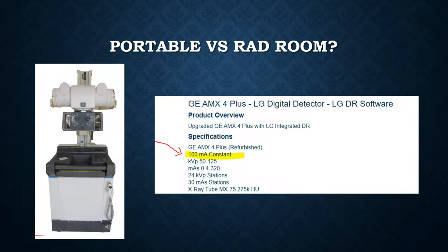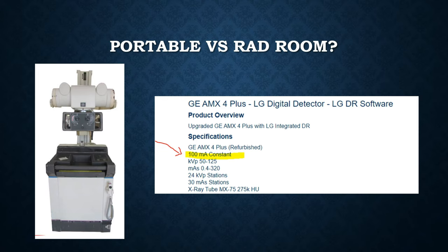Most portable units are set at a fixed 100 mA station. If you need 40 mAs, that becomes a 0.4-second exposure time. That's why you hear that long exposure — it's set at 100 mA fixed, with exposure time calculated accordingly. It's difficult to get a good image on a large patient with a portable. The best option for a KUB is to bring the patient to the room or use a higher mA station to achieve a lower exposure time.